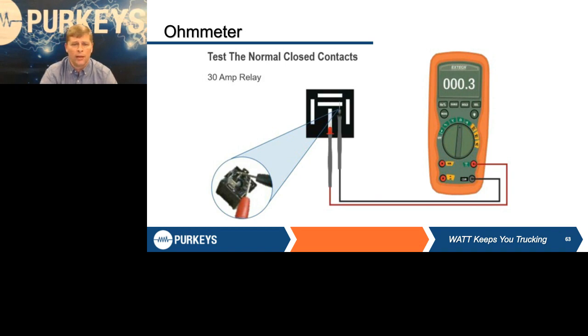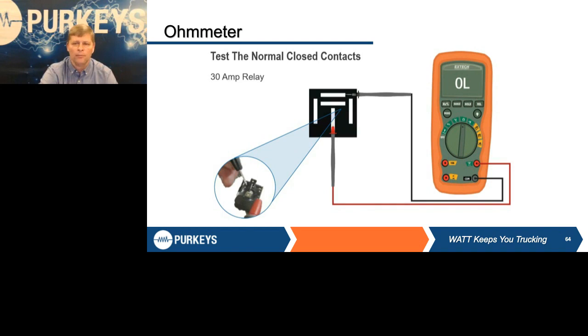The other thing we can do with a relay is check the contacts. If it's a 5-pin relay, it means it has a set of normally closed contacts and a set of normally open contacts. We're going to first check the normally closed contacts. So we're going to put our meter from the common to the normally closed, and we should get a very low resistance reading saying those contacts are closed. We can take our meter and go from the common to the normally open, and we should get an OL saying those contacts are open. Now, if you want to go even further on this, what could you do? You could energize it and make sure the normally open have become closed, and the normally closed have become open.